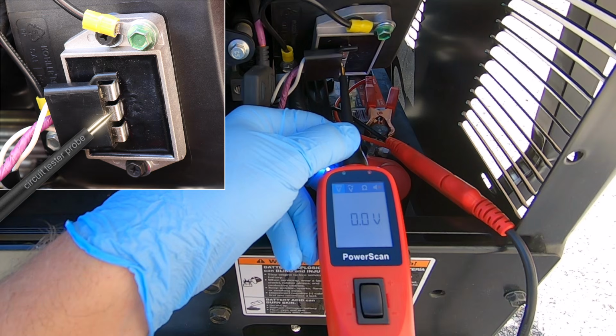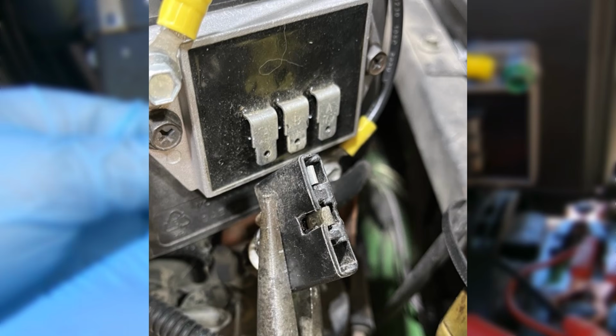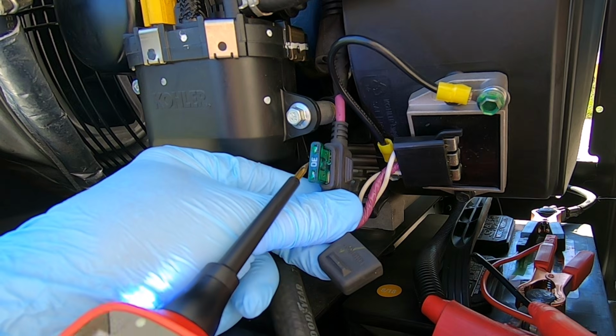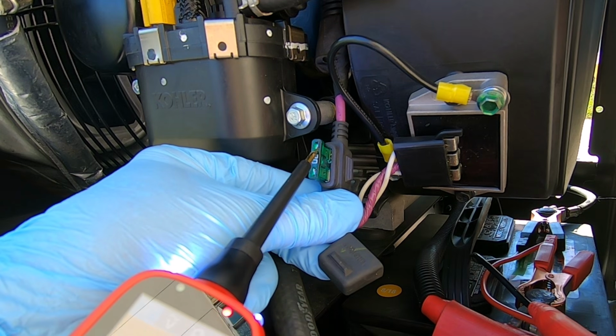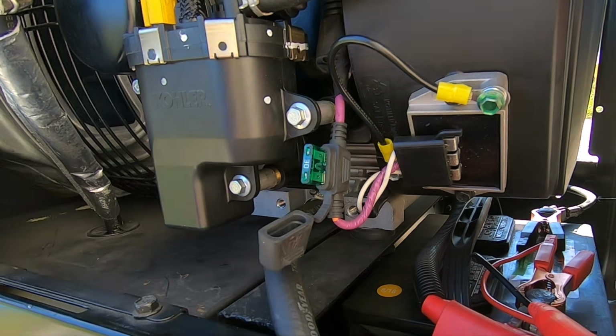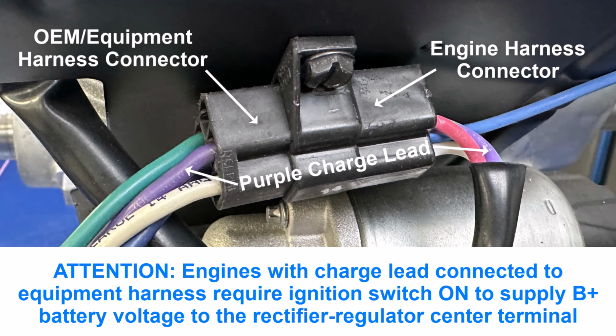If there's no voltage at the center terminal of the rectifier regulator, then there's an open circuit between it and the positive battery terminal. Notice the red LED is off and the screen background is not red, confirming an open circuit. This could be a poor connection or blown fuse. On some applications, the charge lead is routed through the equipment wiring harness and key switch, meaning additional components and connections that need to be inspected.